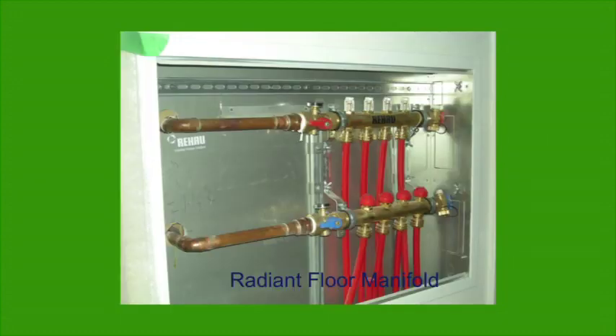So there are 4 circuits here: bedroom, hall, bathroom, vestibule. And we don't really need this for the heating because the house is heated with the air source heat pump. But maybe in 10 years there'll be some renewable source of electricity, or maybe we'll get another circuit off the heat pump that we can heat. Right now we have a small electric water heater that provides the hot water for the floor heating. And it's controlled both by the temperature of the slab and can control on the air temperature, but we'll just control it on the slab temperature to maintain like 22, 24 degrees, so minimal. The main benefit though is from the insulation under the floor.